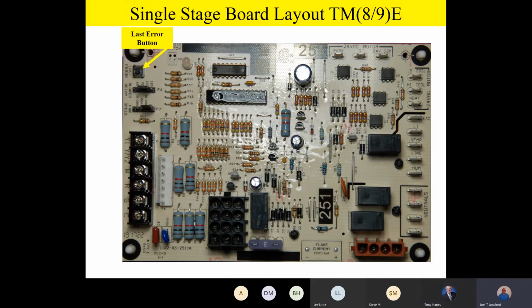All right, team, right above that, we have a last error button. That last error button allows you to go in and pick up the last error codes on the board. The board will remember the last 5 error codes. And you'll notice there's an LED flashing, and what that is, you can actually pick up error codes off that LED. Now, it should be noted that last error button, if you hold that button down about 10 or 15 seconds, it'll clear that error memory. And so, again, you can cycle through and pick up the last 5 error codes.